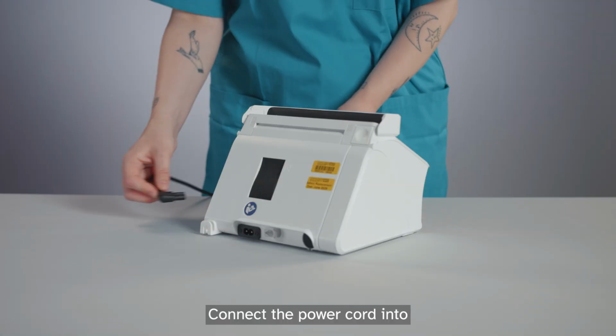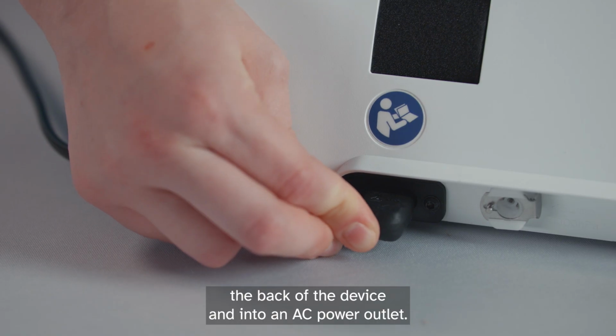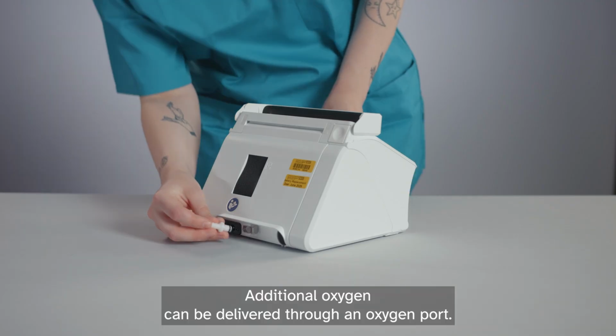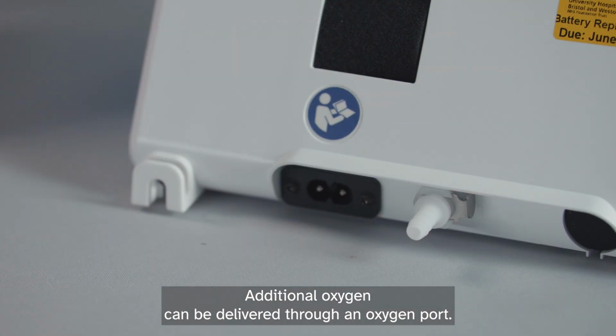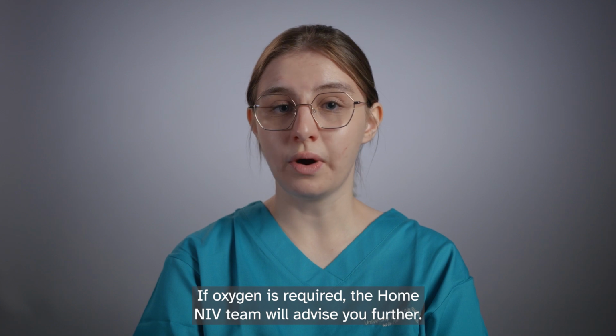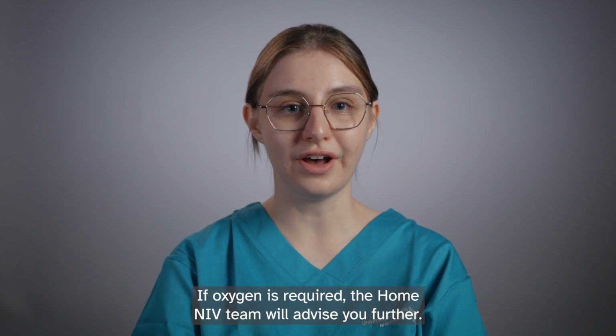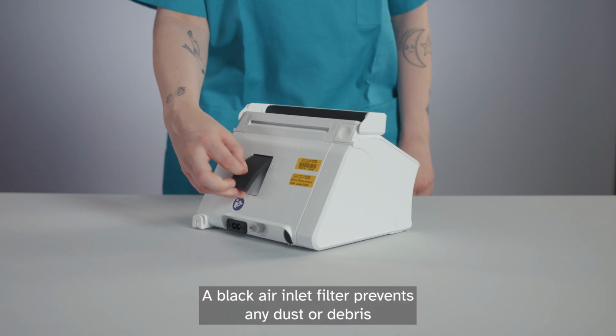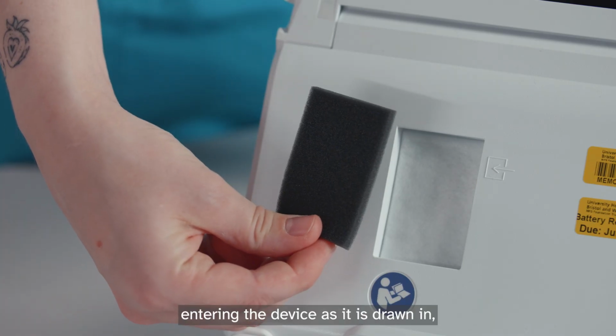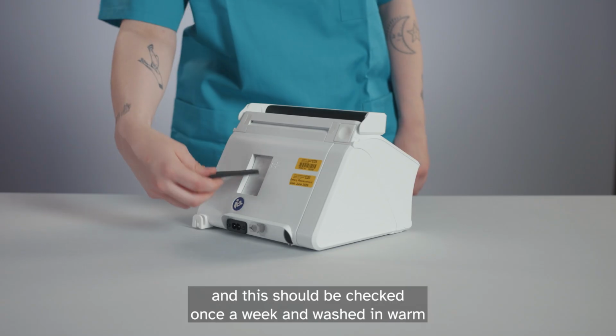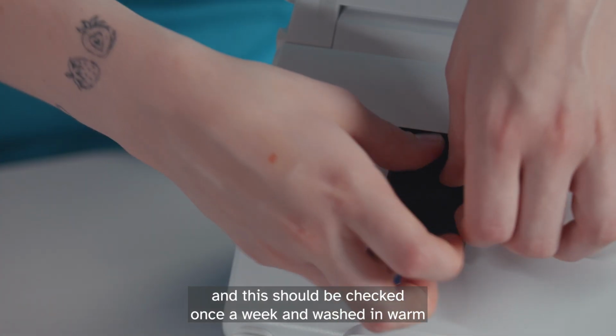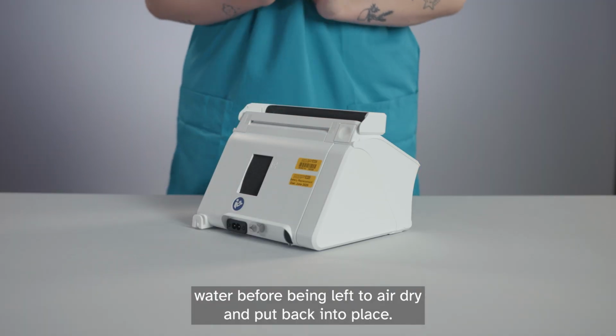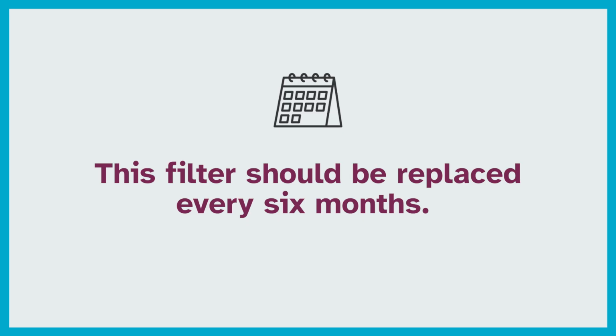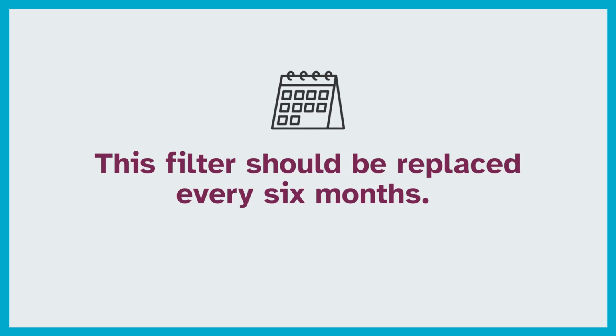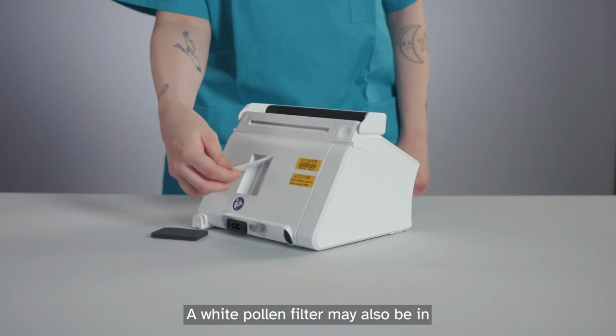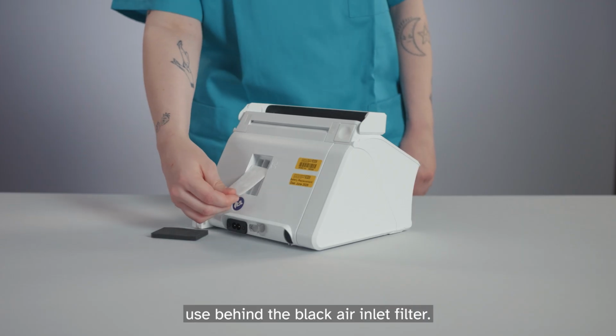Connect the power cord into the back of the device and into an AC power outlet. Additional oxygen can be delivered through an oxygen port. If oxygen is required, the home NIV team will advise you further. A black air inlet filter prevents any dust or debris entering the device as it is drawn in, and this should be checked once a week and washed in warm water before being left to air dry and put back into place. This filter should be replaced every 6 months. A white pollen filter may also be in use behind the black air inlet filter.